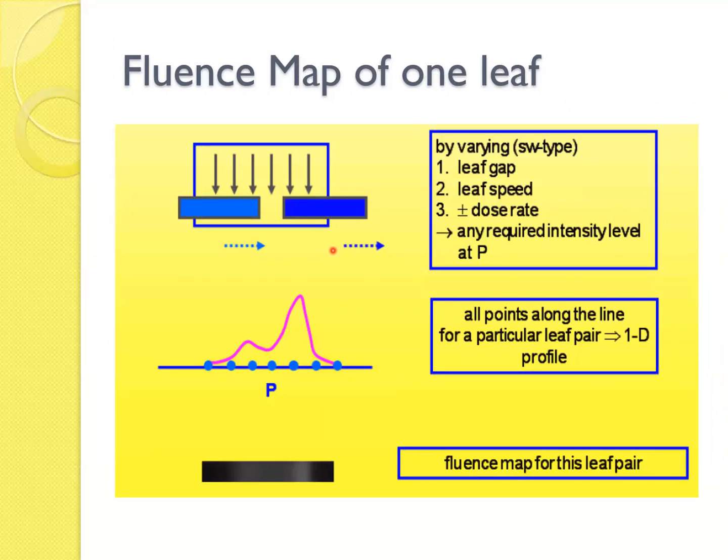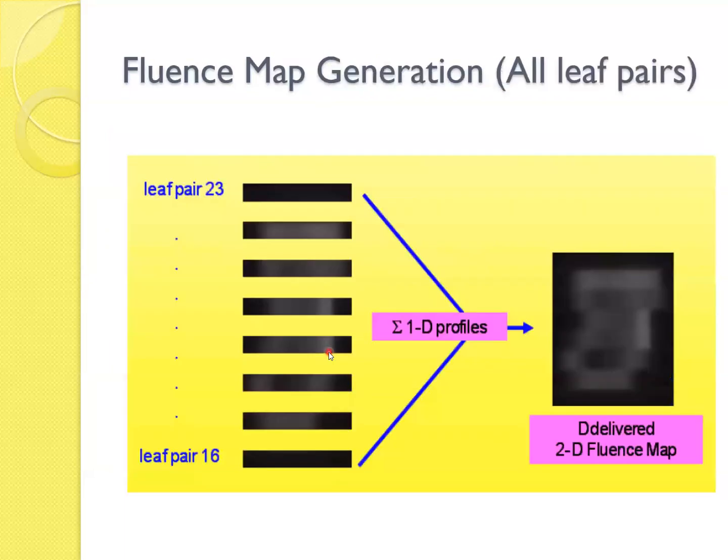And this is another visual example of how the fluence is generated, how the MLCs are moving from one end to the other end. So by varying the sweep type, the leaf gap, leaf speed, dose rate, all are very important to consider. And also for the quality assurance, these need to be considered. There are AAPM guidelines available for the MLC QA. All going along the line for the particular leaf pair and the 1D profile. And fluence map for this leaf pair and the film. And this is 1D profile converted into 2D profile.